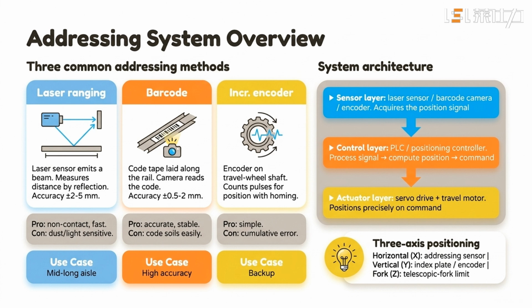Note that the addressing system isn't just one sensor. It's a 3-layer architecture, sensor plus controller plus actuator. And remember one principle: the stacker positions on 3 axes, horizontal by the addressing sensor, vertical by the encoder, and the fork by the telescopic fork limit.